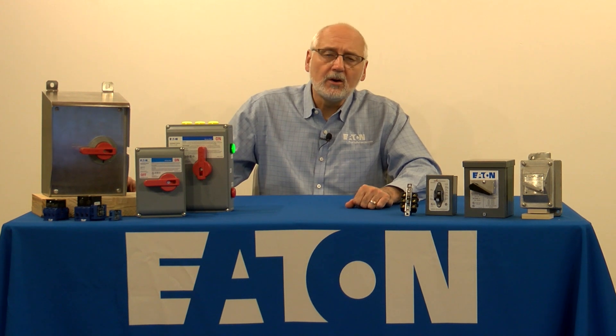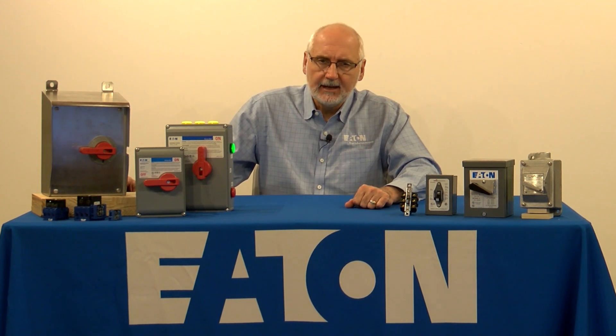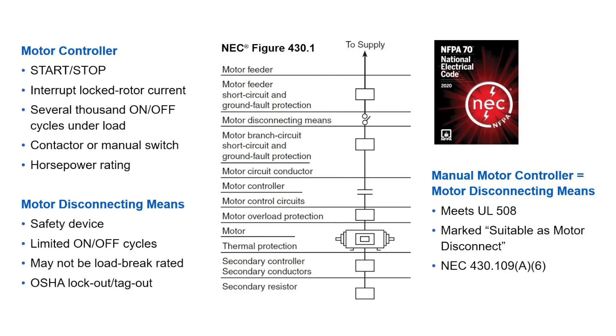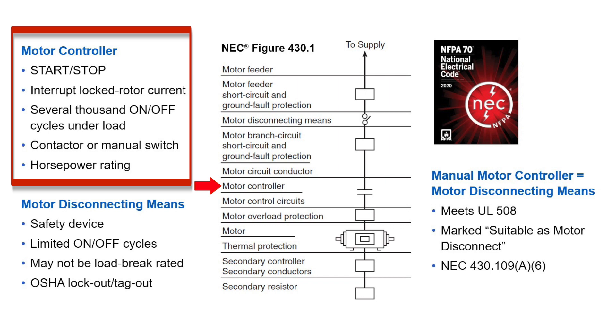So how do we control all that horsepower? Let's take a quick look at the code requirements for motor controllers and disconnects. A motor circuit has many parts — here's a diagram showing each one in its relative location. A motor controller is any switch or device used to start and stop a motor by making and breaking the motor circuit current, and it must be capable of interrupting the locked rotor current of the motor. It's designed for several thousand on and off cycles under load and will generally be either a contactor or a manual switch.